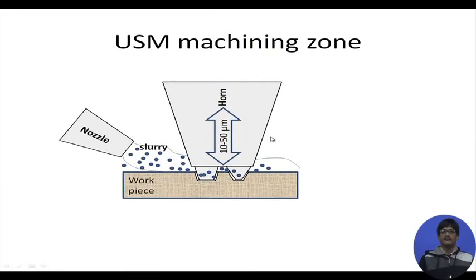So, let us have a look at the ultrasonic machining zone, or the actual site of machining. We have demarcated the tool by a trapezium, by 2 trapeziums basically. That means the opposite of this shape is going to be produced on the workpiece. Here we have shown that the amplitude of vibration at this end is 10 to 50 microns. That means it may be 10, it may be 20, it may be 50, like that. So, this is the end of the horn, the tool end of the horn. From the nozzle, slurry is coming out, which means that in a water medium you are carrying abrasive particles. So, these abrasive particles are everywhere, and after use they are getting deposited somewhere, and the recommended practice will be not to recycle them.